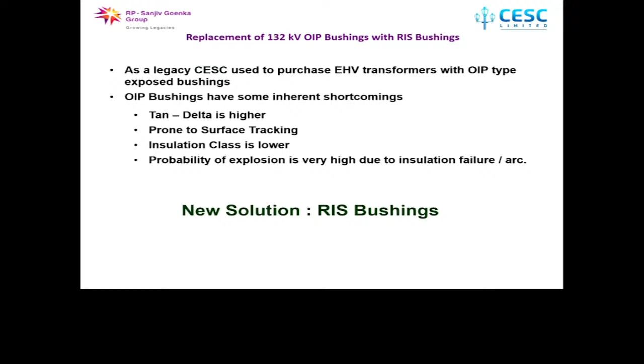I'll complete. We have had a bad experience on a couple of occasions. We have seen bushings explode, maybe due to high PD, or tracking, or after repeated failure due to short circuit by some external object. There may be internal cracks in the bushings, and they tend to fail.